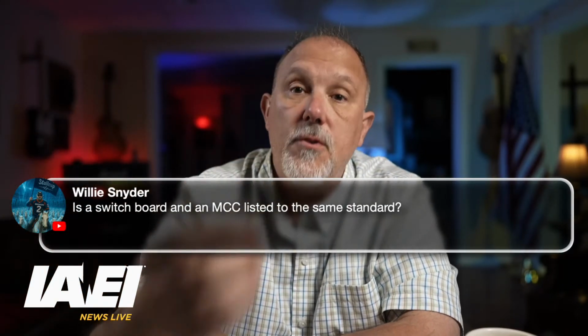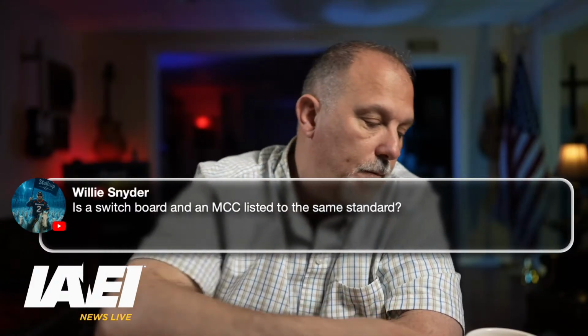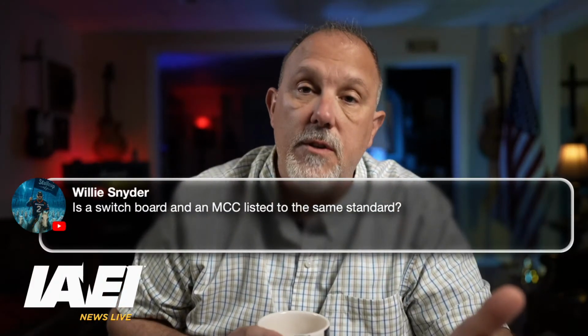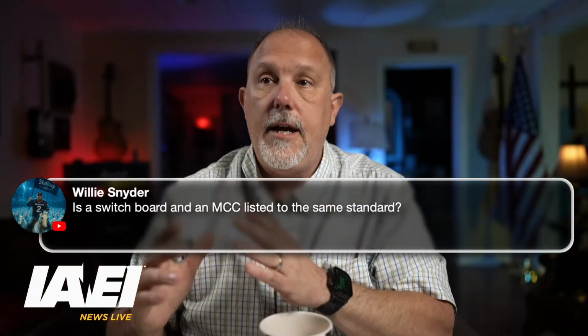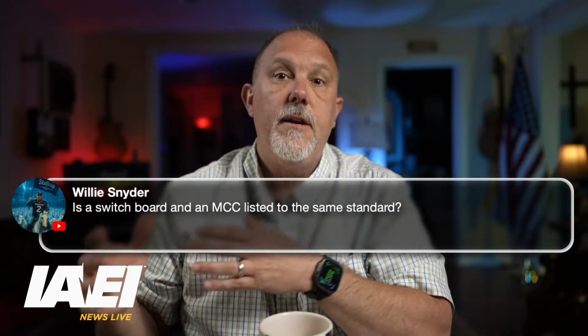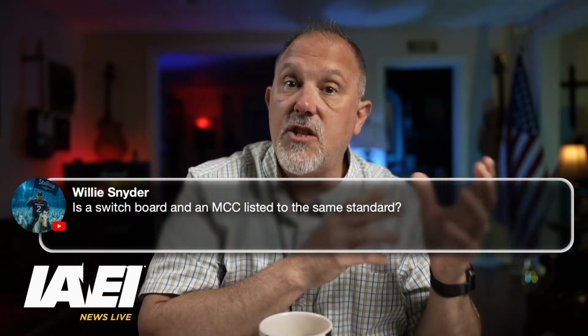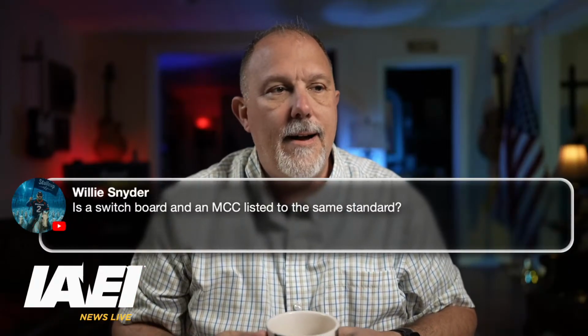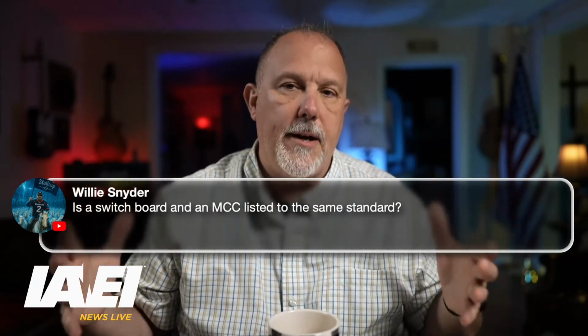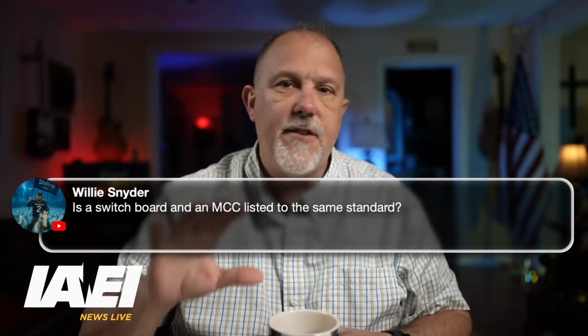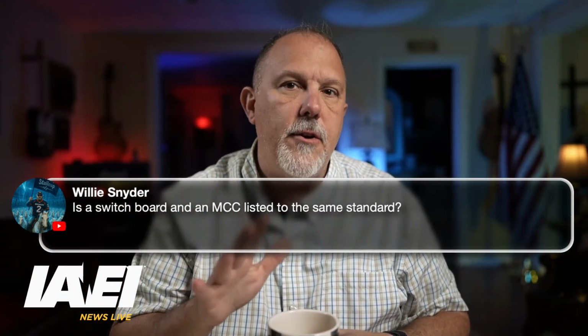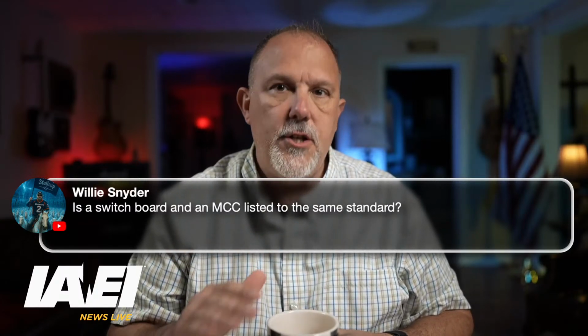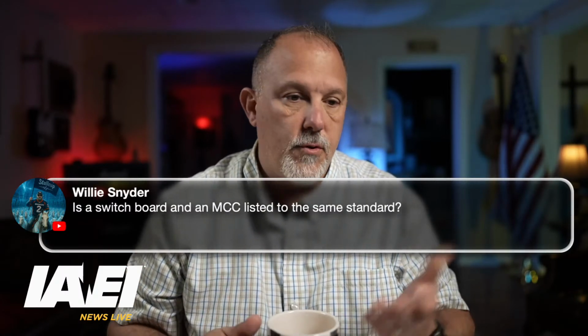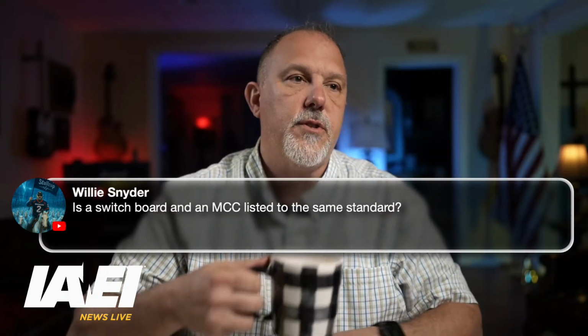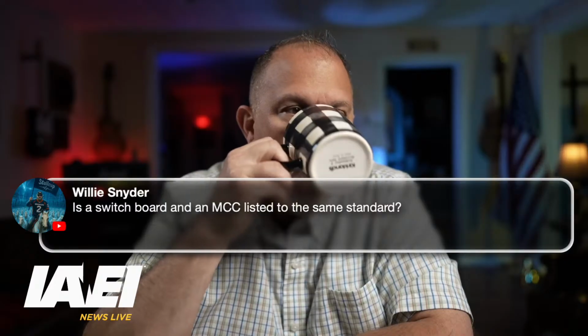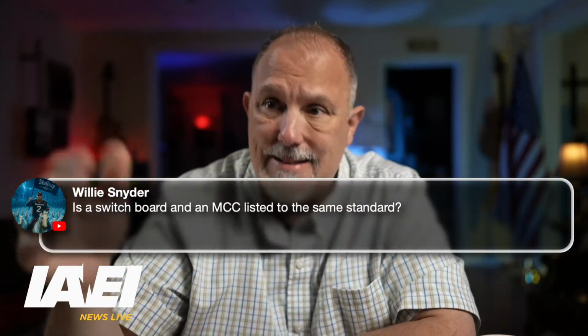So now a motor control center is similar in flexibility to a switchboard, because I can do a lot in a motor control center. Very similar to what I can do in a switchboard. Switchgear, I've got that—that's your big breakers, your big power circuit breakers. I can have controls and whatnot, cubicles for controls, but I'm not going to do with switchgear what I can do with a switchboard and a motor control center, for all that matters. I've not seen a motor control center with a panel board inside—not to say they don't exist.